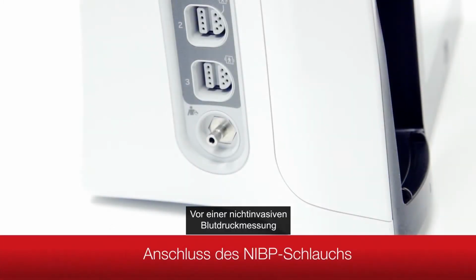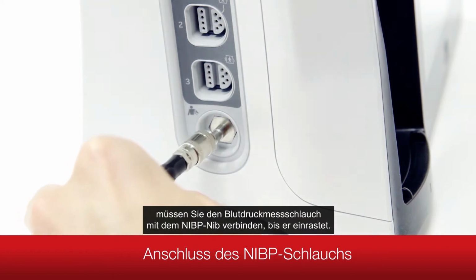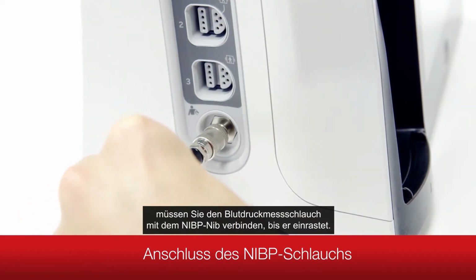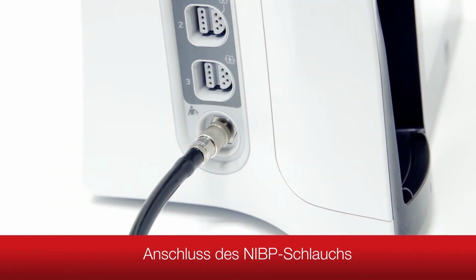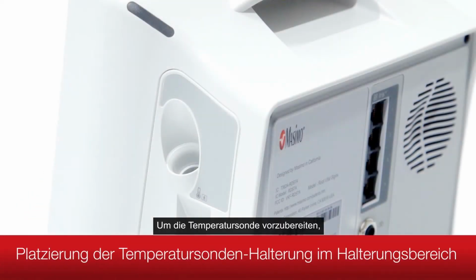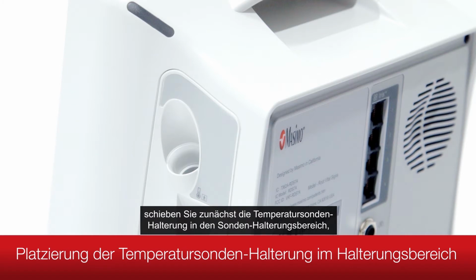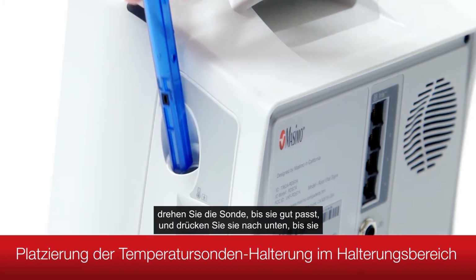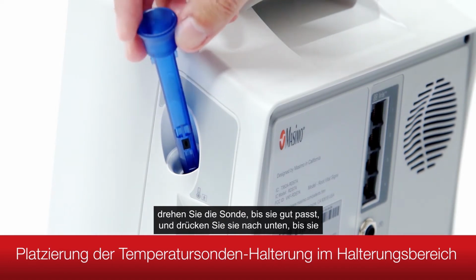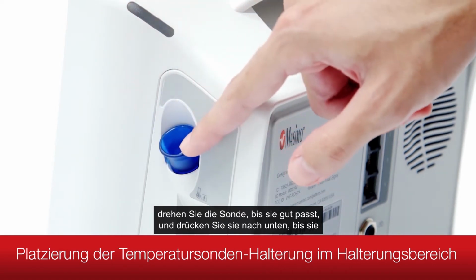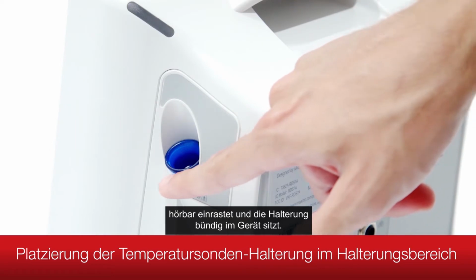Before you can take a non-invasive blood pressure measurement, you must connect the blood pressure hose to the NIBP nib until it clicks into place. To set up the temperature probe, begin by sliding the temperature probe well into the probe well area. Rotate until it fits in easily and push down until you hear a click and the well sits flush with the device.